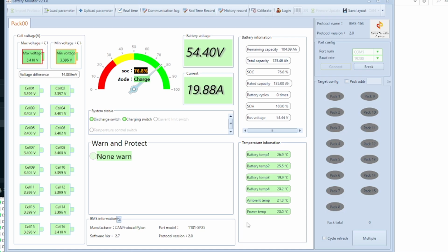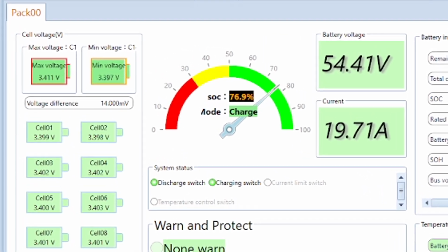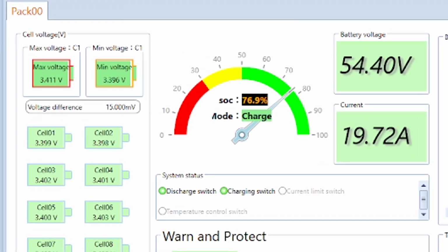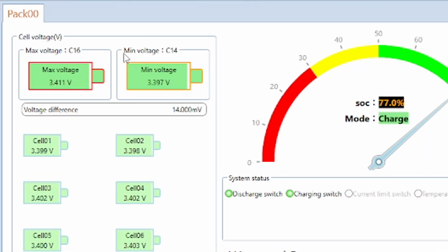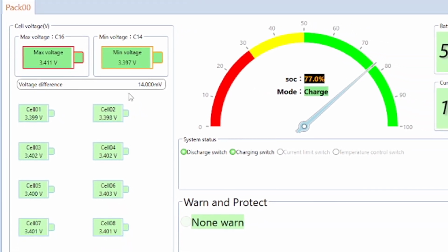We want to have a quick look at our software. We have a deviation of 14 millivolts right now, but we're only at 77% state of charge, so still in the flat area of the curves. Up here it shows cell number 1 as highest, no actually I can't see that, now I can see it. Cell number 16 is our highest cell, and cell number 14 is our lowest.